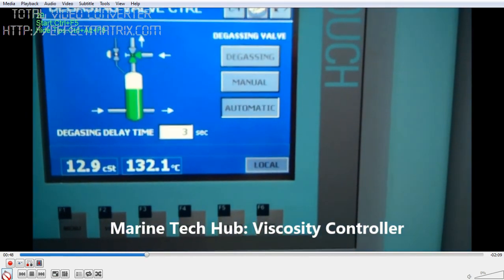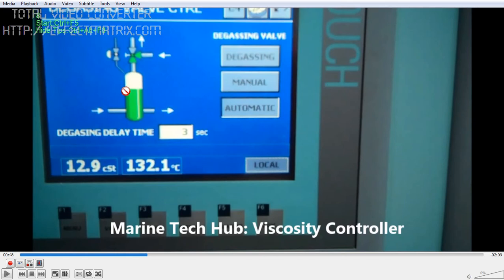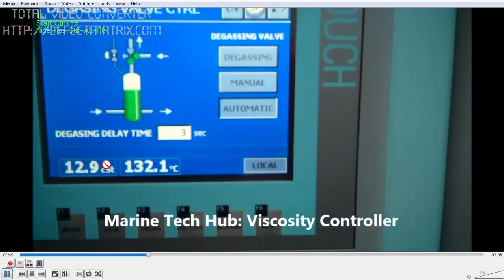This is the degassing system. Suppose there is gas formation — it will automatically open and release the gas so that there will be no vapor lock in the system. If there is a vapor lock, the fuel will not flow and the main engine can stop, or even the generator can stop. So we have this system in place.